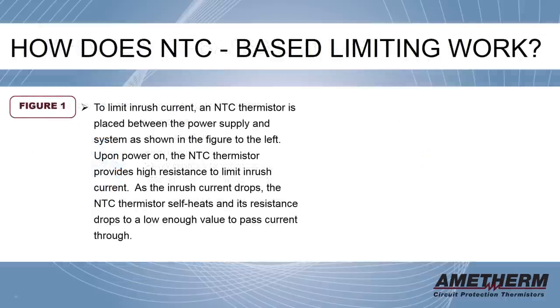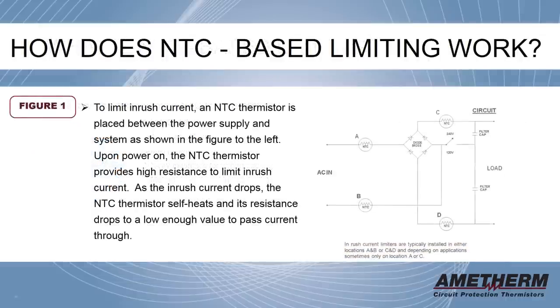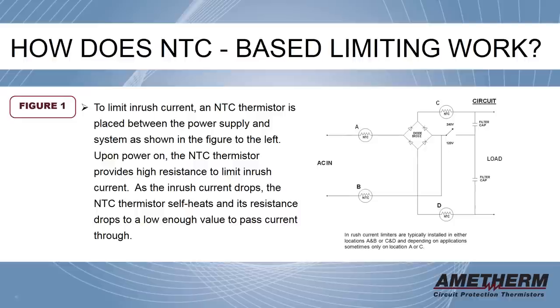How does NTC-based limiting work? To limit inrush current, an NTC thermistor is placed between the power supply and system as shown in the figure to the left. Upon power on, the NTC thermistor provides high resistance to limit inrush current. As the inrush current drops, the NTC thermistor self-heats, and its resistance drops to a low enough value to pass current through.